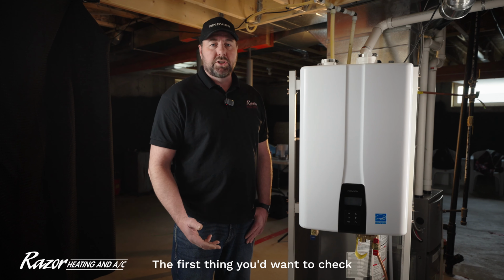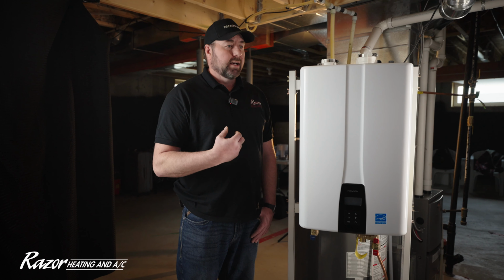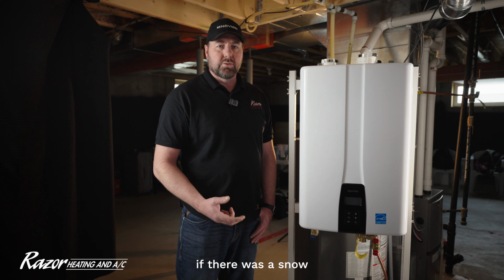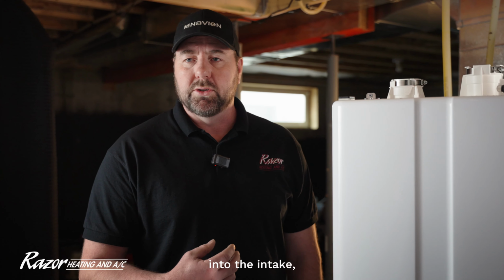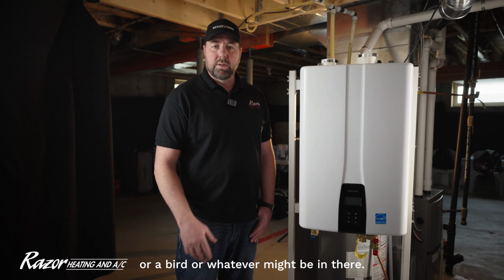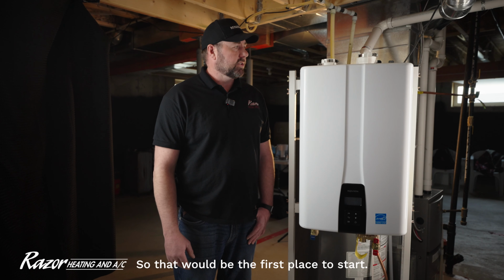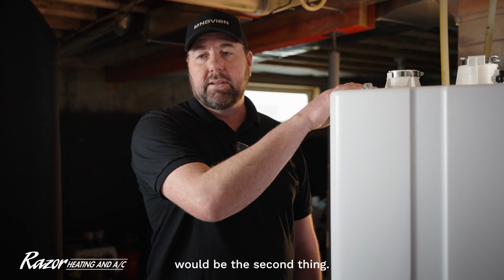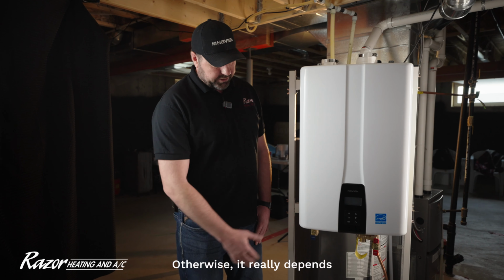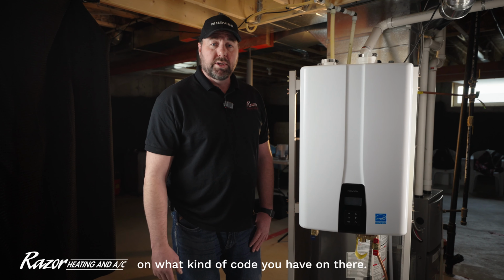The first thing you'd want to check would be the venting outside. If it happened to freeze up, if there was a snowstorm or something like that, you can suck some snow into the intake, which can freeze it, or a bird or whatever might be in there. So that would be the first place to start. The air intake screen would be the second thing. Otherwise, it really depends on what kind of code you have on there.